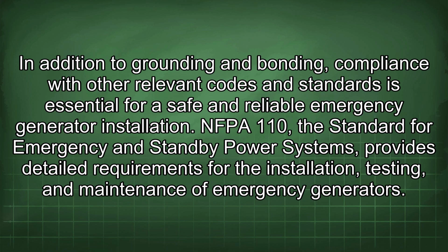In addition to grounding and bonding, compliance with other relevant codes and standards is essential for a safe and reliable emergency generator installation. NFPA 110, the standard for emergency and standby power systems, provides detailed requirements for the installation, testing, and maintenance of emergency generators.